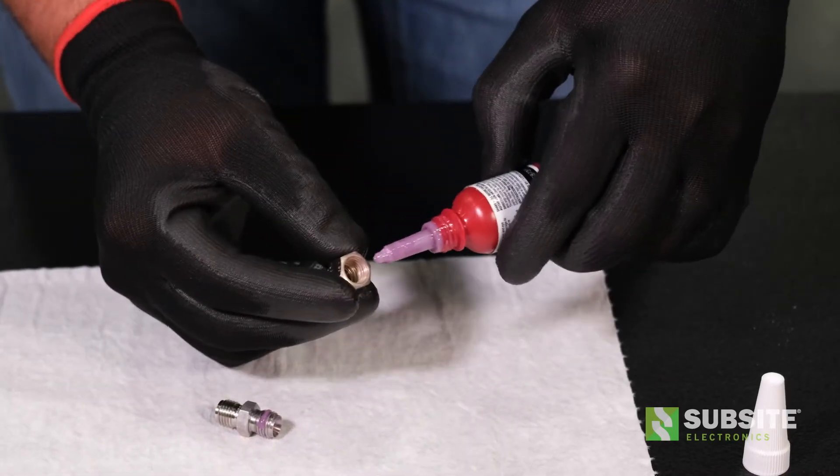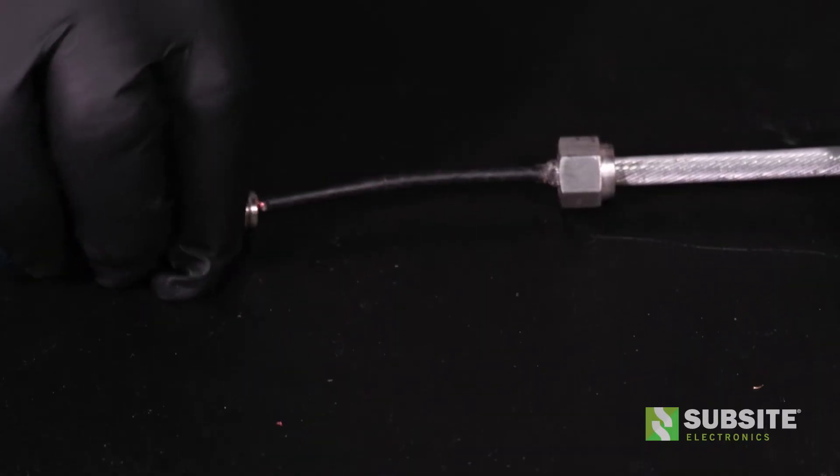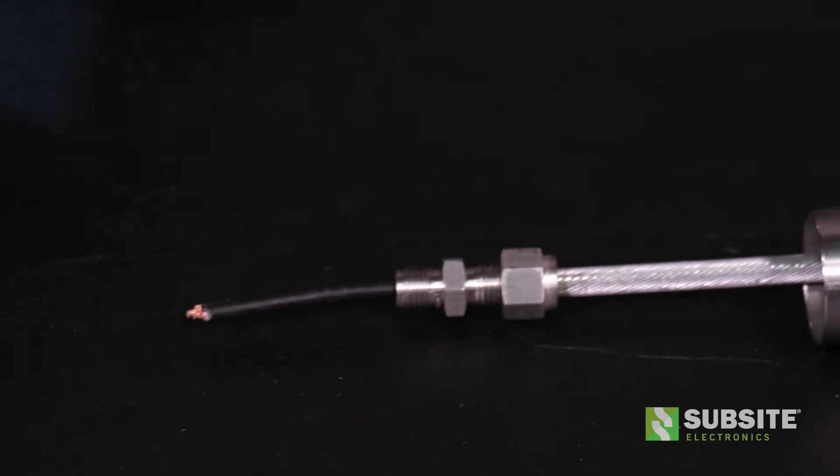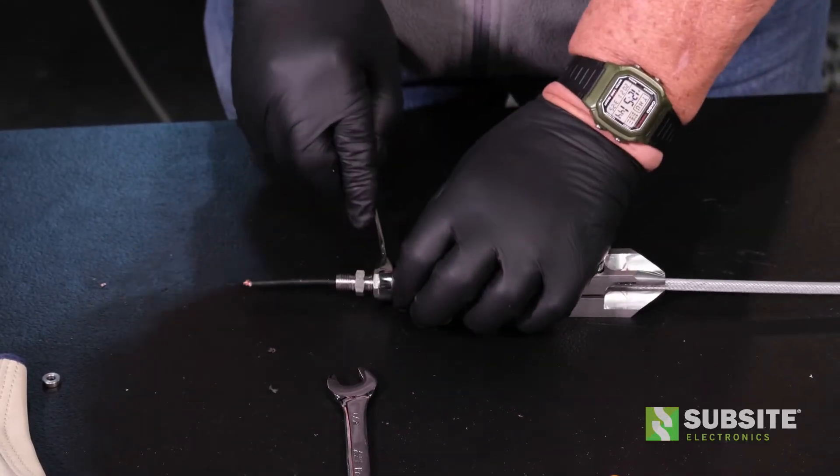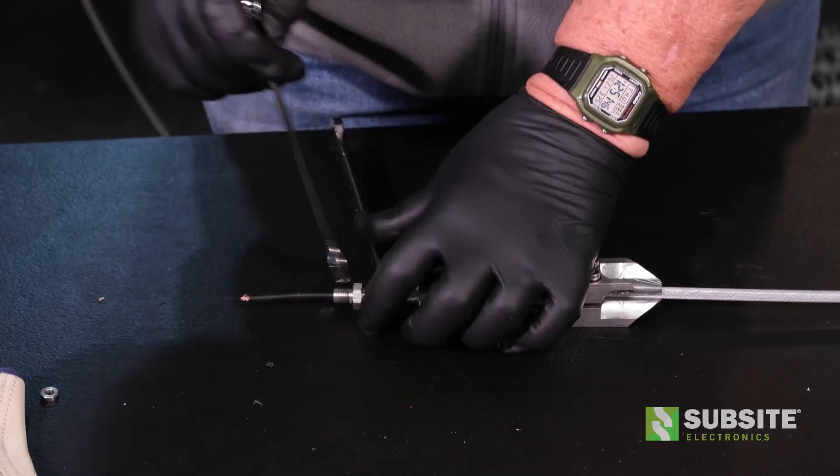Apply purple Loctite to the threads of the ferrule nut. Then insert the cable through the ferrule body and tighten. Use the 9/16 inch wrench to hold the ferrule nut while using the 1/2 inch wrench to tighten the ferrule body.